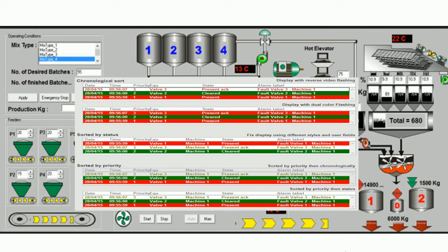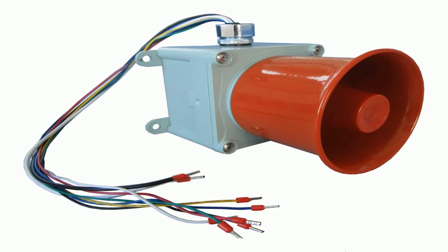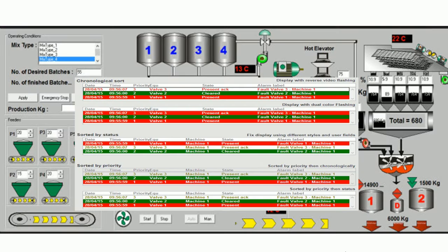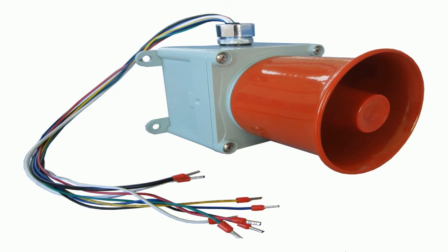Once an alarm event has been detected, one or more actions are taken, such as the activation of alarm indicators and perhaps the generation of email or text messages. Integrated into the data and graphical displays are alarm functions that can raise and display alarms as they occur. On some systems, they can be tied into auto-paging and auto-phone dialing features that will automatically notify operating personnel of a problem, so that management or remote SCADA operators are informed. In many cases, a SCADA operator may have to acknowledge the alarm event, which may deactivate some alarm indicators, whereas other indicators remain active until the alarm conditions are cleared.